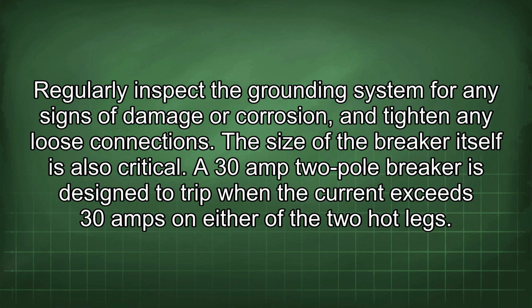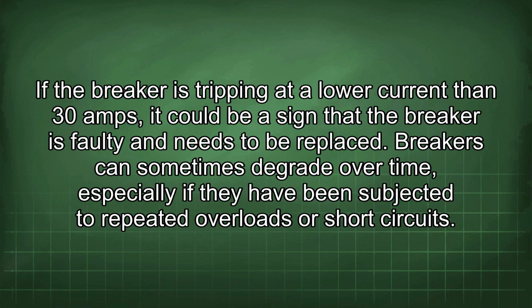The size of the breaker itself is also critical. A 30 amp 2-pole breaker is designed to trip when the current exceeds 30 amps on either of the two hot legs. If the breaker is tripping at a lower current than 30 amps, it could be a sign that the breaker is faulty and needs to be replaced. Breakers can sometimes degrade over time, especially if they have been subjected to repeated overloads or short circuits.